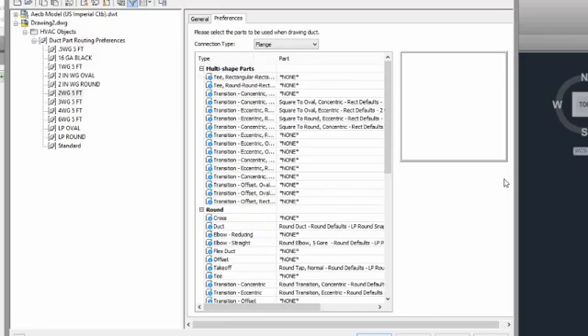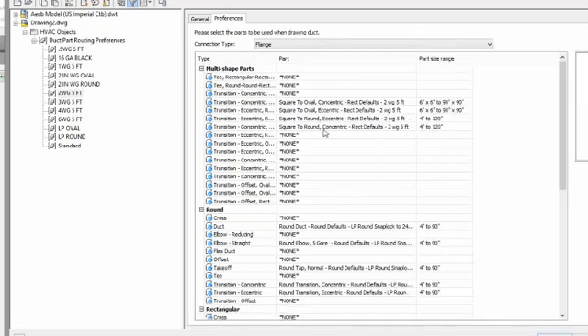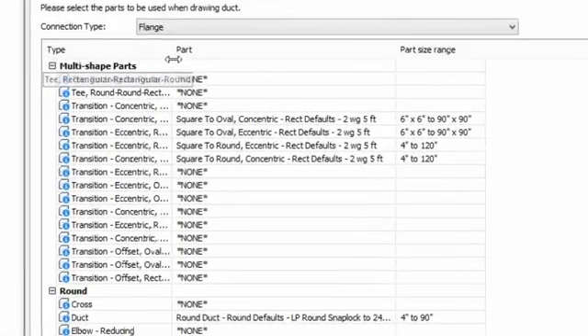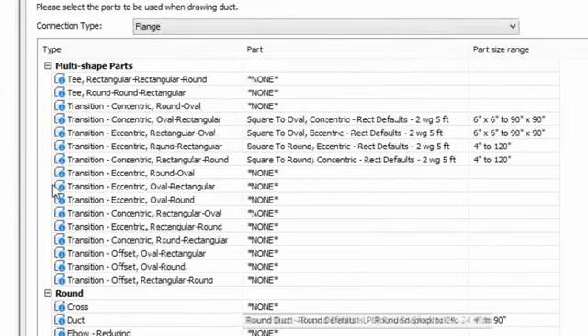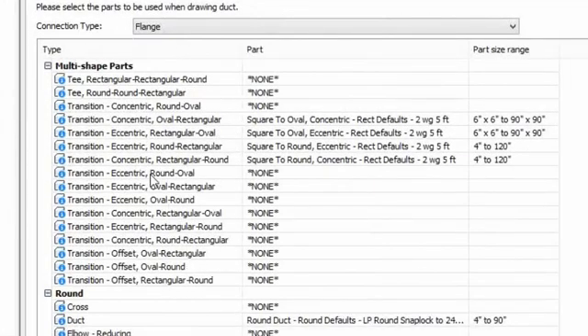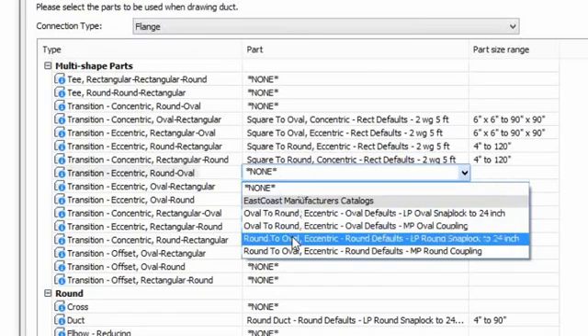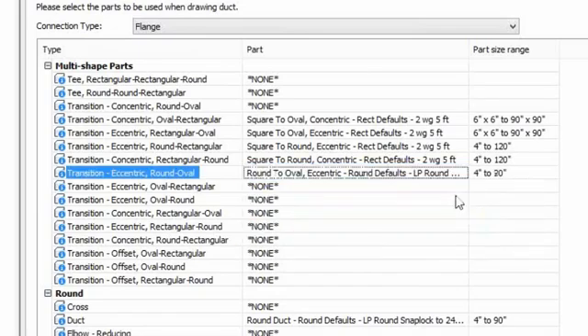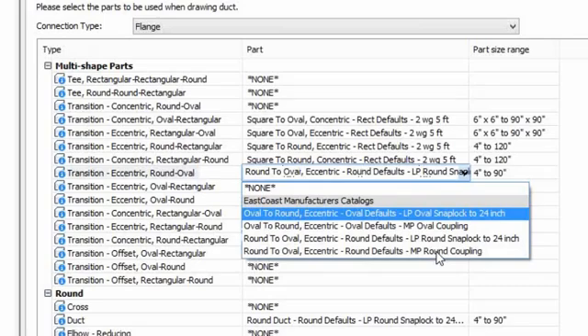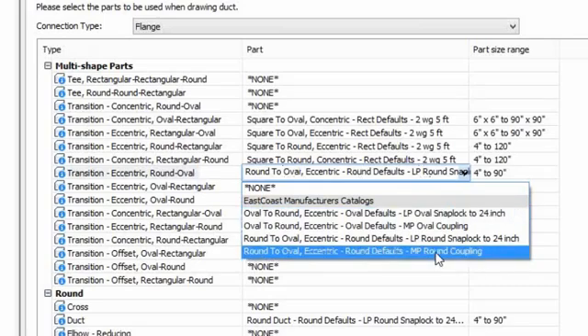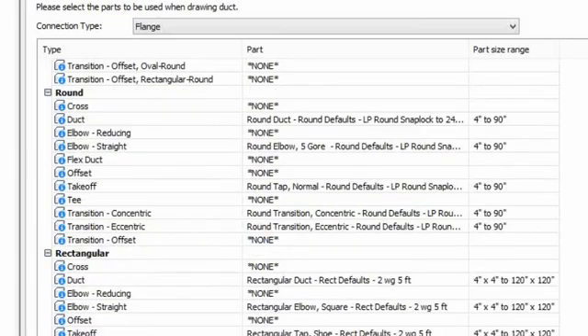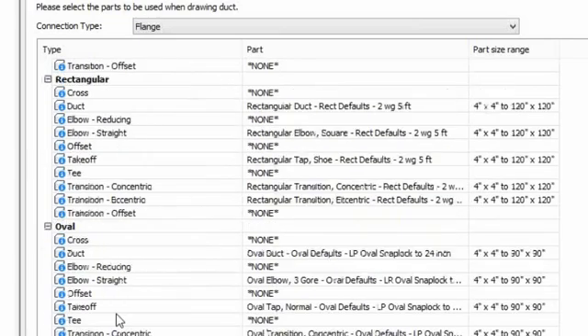So basically what you would do for each of these parts, you would come in and you would set the part that you would like to see automatically added. So for a transition round to oval eccentric, I'm just going to choose a round to oval LP Snaplock because I'm on my 2-inch pressure class. Maybe if I was on my 6-inch pressure class, instead of the LP round, I would choose the medium pressure. So you just come through, your round to rectangular, your oval, and you go ahead and you set the default parts that you want to see.